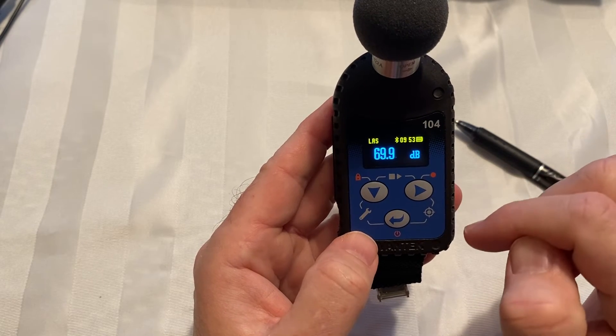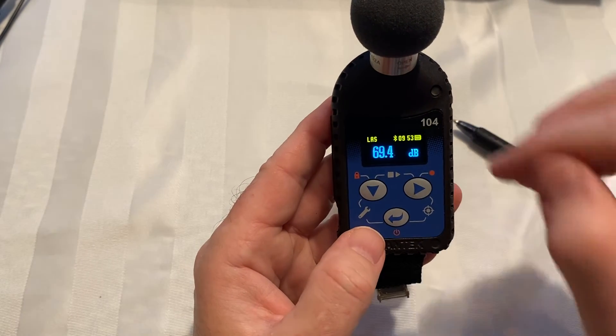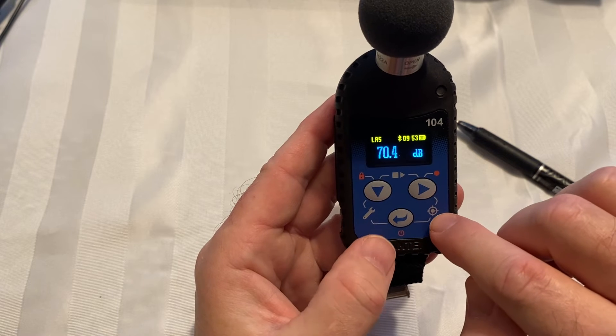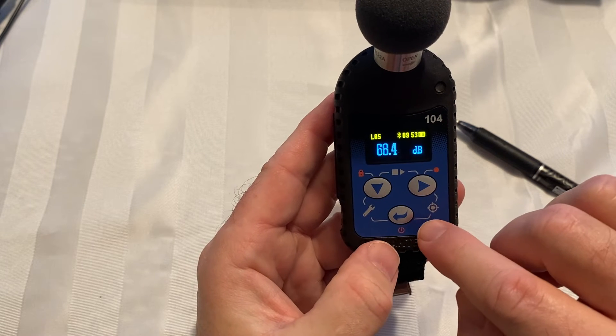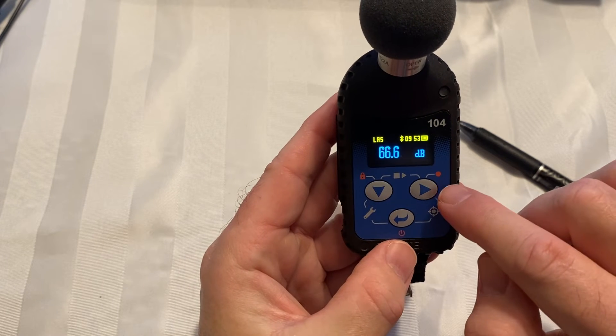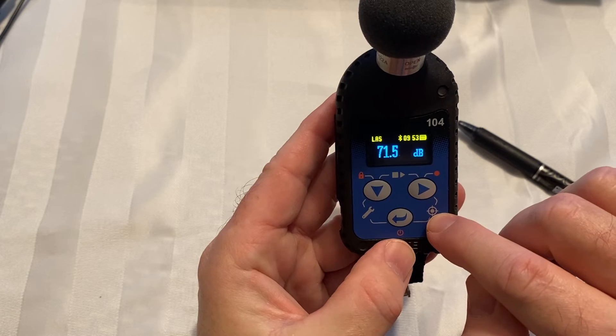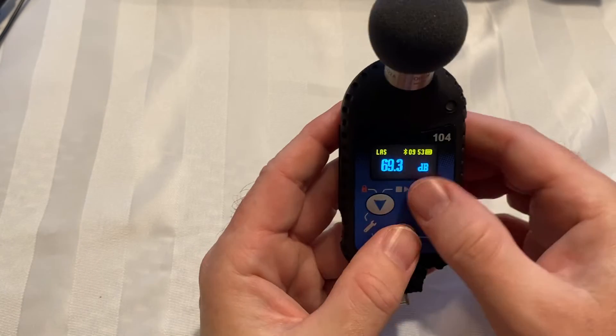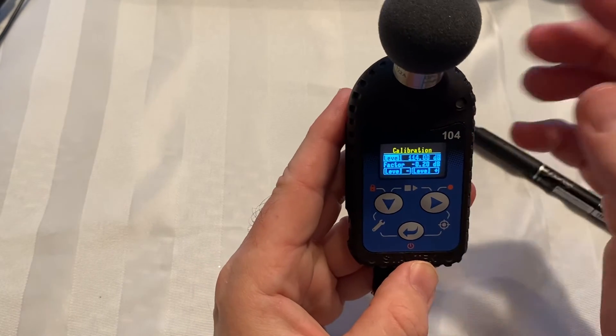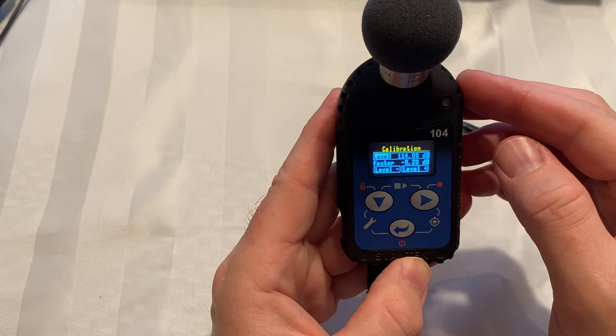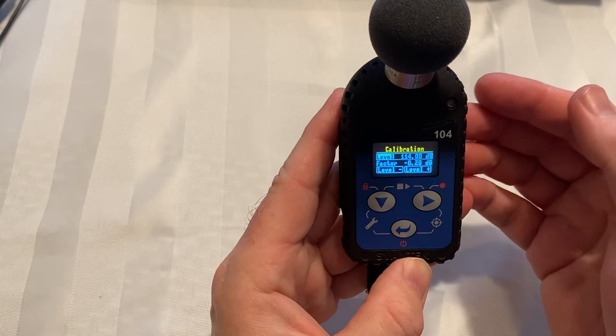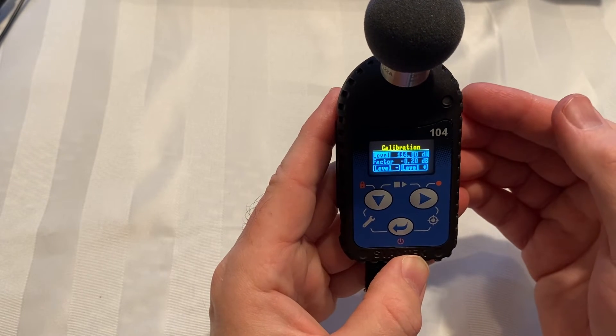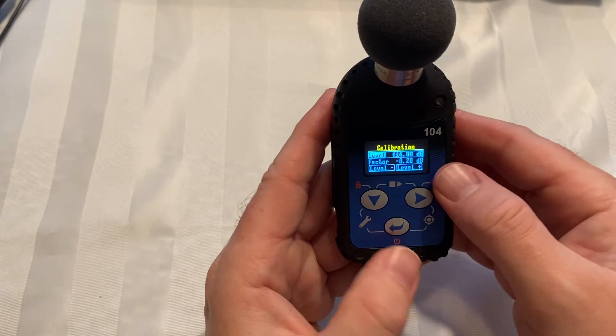Now there's a way to use them together as well. If I hit the enter and right key together, this forces the calibration. So let's hit both of those, and now I could put the calibrator on, do the calibration before the measurement and after the measurement to make sure there was no drift.